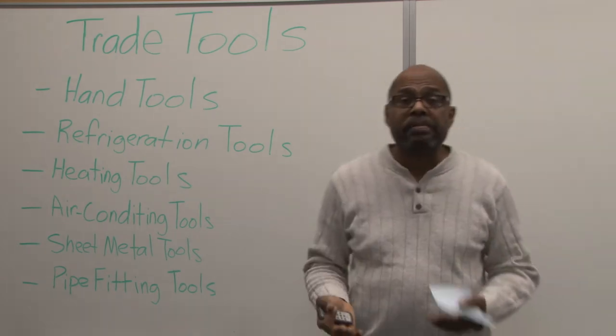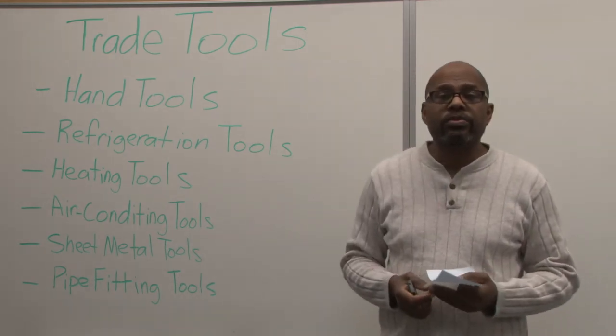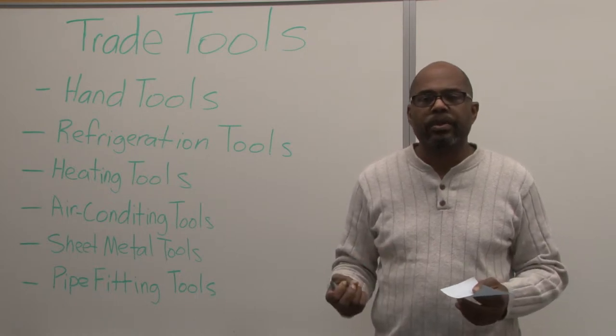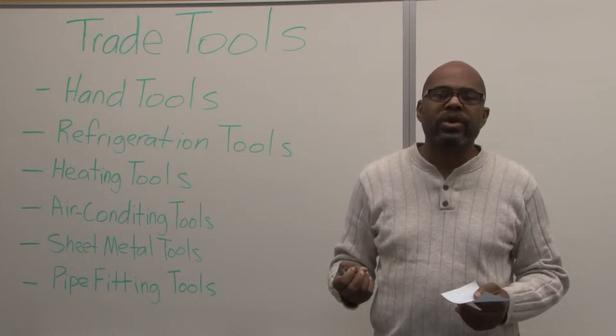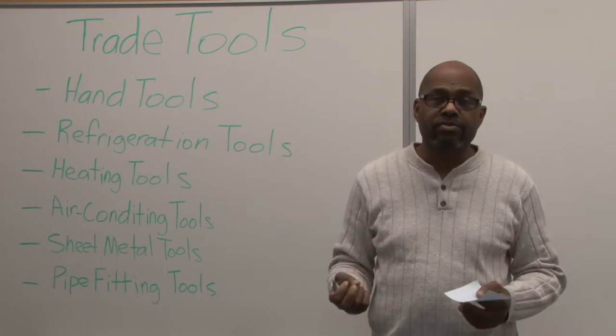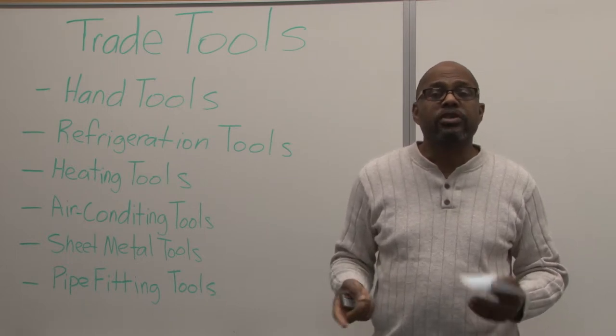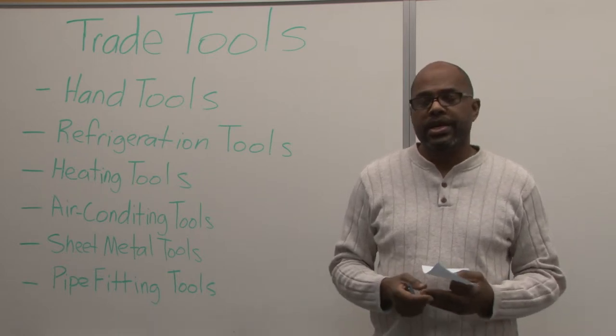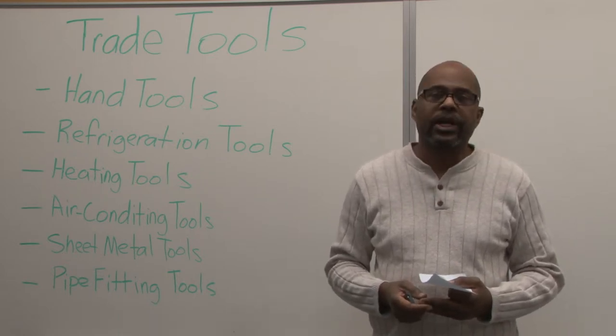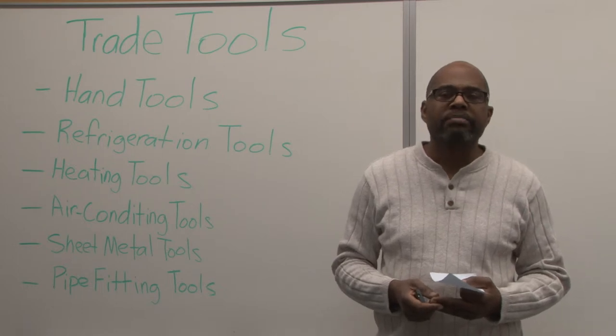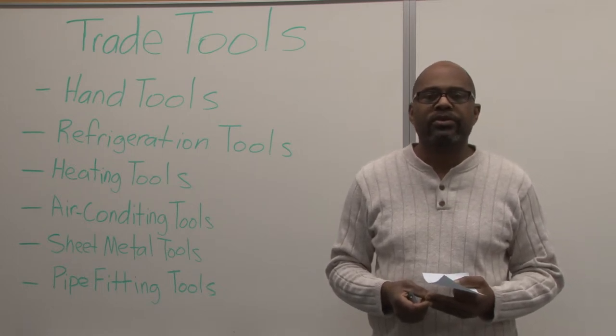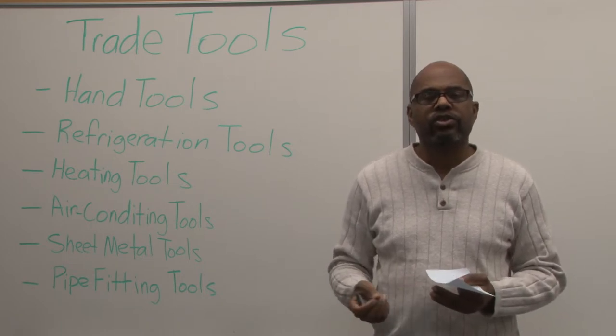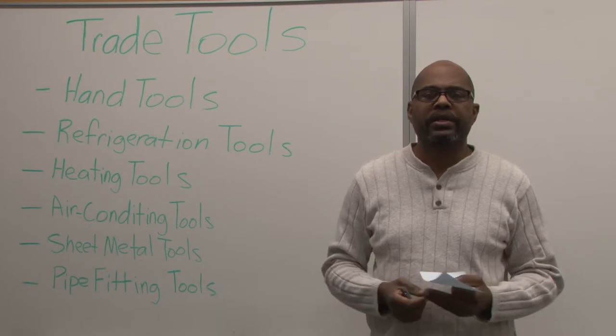Heating tools are special tools. Most heating systems that use gas use some type of flame rectification system where it actually reads the microamp reading through the flame. You need a special meter that can read very low current through that circuit. Having a microamp meter would be advisable because if not, you wouldn't know if the flame sensor is actually making contact or is working correctly.